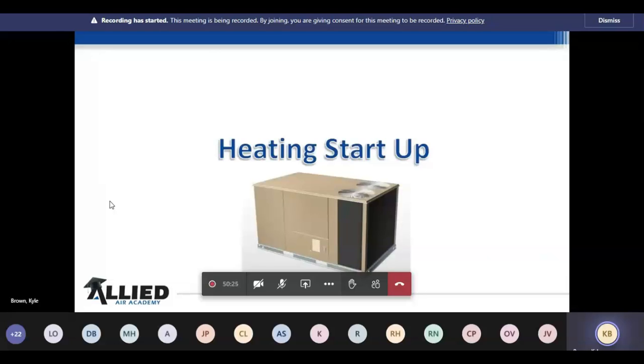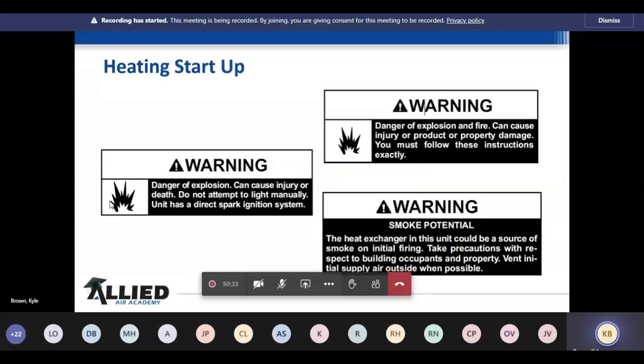Now we want to do the heating startup. That's the cooling startup. And I very rarely do any type of heating. I want to talk about a heating startup, and you want to make sure all these labels. Unfortunately, we live in the world where you've got to be careful. You don't want any damage to the building or any damage to anybody themselves, or personal injury to happen. So it's important to know the warning stickers should not be taken off.